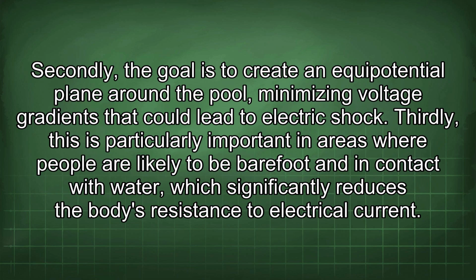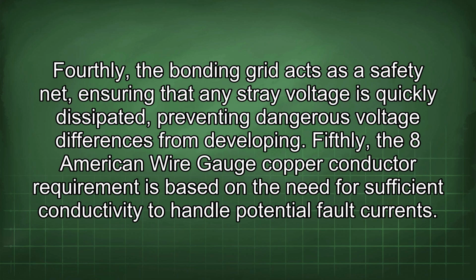Secondly, the goal is to create an equipotential plane around the pool, minimizing voltage gradients that could lead to electric shock. Thirdly, this is particularly important in areas where people are likely to be barefoot and in contact with water, which significantly reduces the body's resistance to electrical current. Fourthly, the bonding grid acts as a safety net, ensuring that any stray voltage is quickly dissipated, preventing dangerous voltage differences from developing. Fifthly, the 8 American wire gauge copper conductor requirement is based on the need for sufficient conductivity to handle potential fault currents.